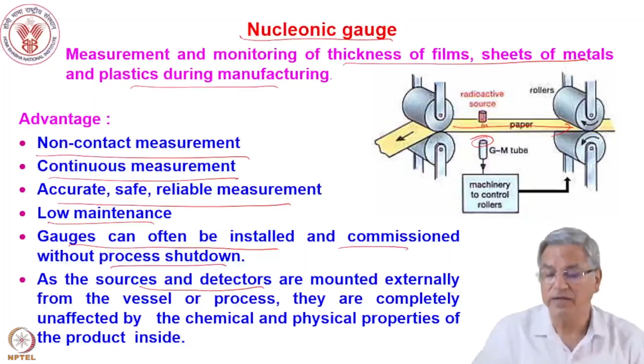These gauges have the advantage of non-contact measurement. You can place them even while the plant is running, allowing continuous measurement that is accurate, safe, and reliable. There's hardly any maintenance, and the plant doesn't need to shut down - gauges can often be installed and commissioned without process shutdown. Since the sources and detectors are mounted externally from the vessel or process, they're completely unaffected by the chemical and physical properties of the product. It's non-invasive - the plant keeps running, and you can do all modification to determine thicknesses without affecting the plant. That's the kind of advantage with this.